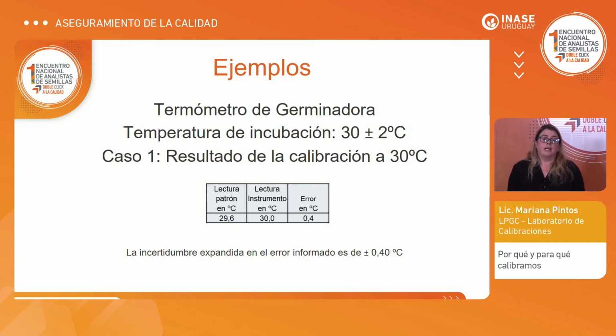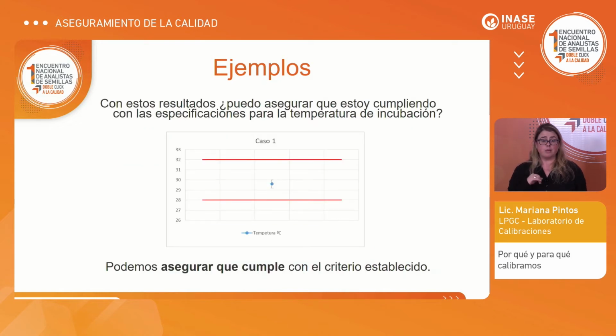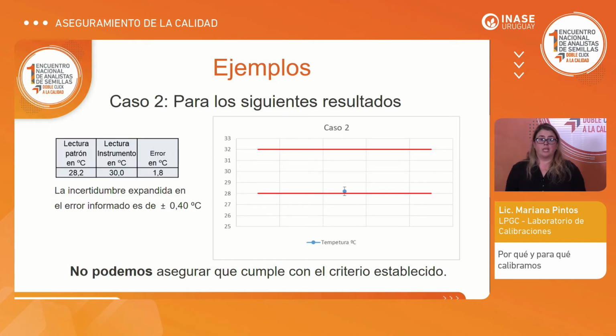In one case, we are going to see the result when we are setting the germinator to 30. We have a reading of 29.6 in comparison to the pattern. So the uncertainty informed is 0.4. So my value can change from 29.2 to 30. Let's see it in a chart. This is a value we got, and the temperature area where we can vary, so there can be an uncertainty. So we can see that we are inside the tolerance, so we can assure that we are meeting the established criteria.